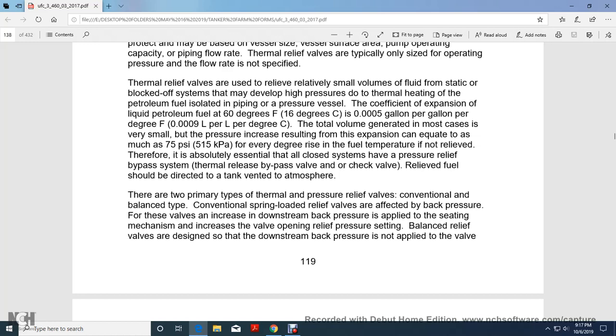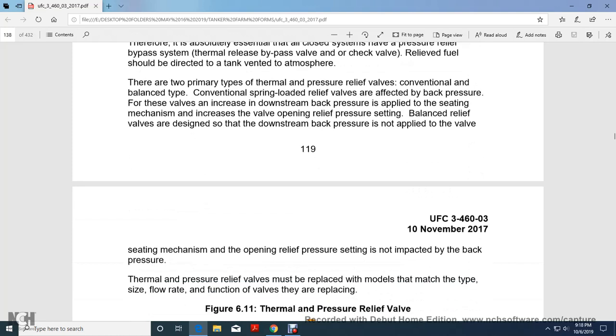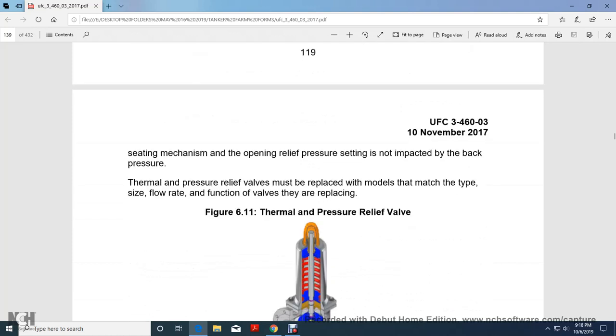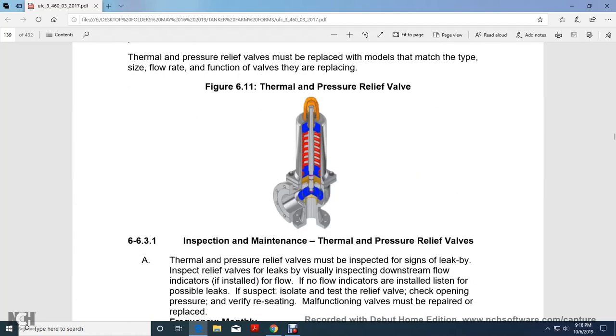There are two primary types of thermal pressure relief valve: conventional and balanced. The conventional spring-loaded relief valves are affected by back pressure on the valves. Increased downstream back pressure is applied to the seating mechanism and increases the valve opening pressure of the relief setting. Balanced reliefs are designed so downstream back pressure is not applied to the valve seating mechanism. The opening pressure of the relief setting is not impacted by the back pressure. Thermal pressure relief valves must be replaced with valves matching the type, size, flow rate, and function of the valves they are replacing. 6.11 shows the thermal pressure relief valves.